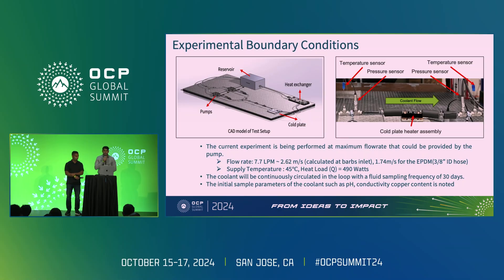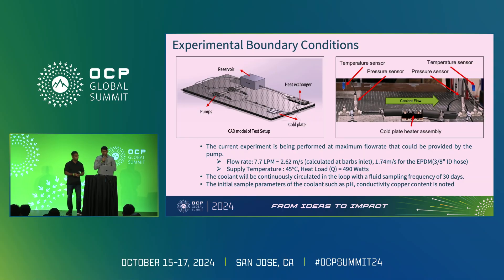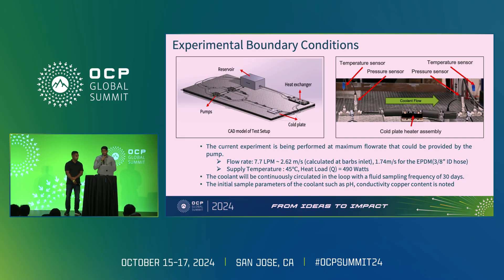The main observation for us is to see if there is any erosion inside the copper cold plate, and from the coolant side, we would be seeing it through increasing copper content. To avoid copper presenting in any other components, we made sure the closed loop is made from all stainless steel components — like the heat exchanger, the pump casing, the fittings used for the thermocouple and pressure sensors. Only the copper present in the loop was from the cold plate, so if any copper is seen in the coolant, that would be the only source. The pressure and temperature sensors were all calibrated using standard calibration techniques, and the slope and offset values were given into the data acquisition systems to minimize error.